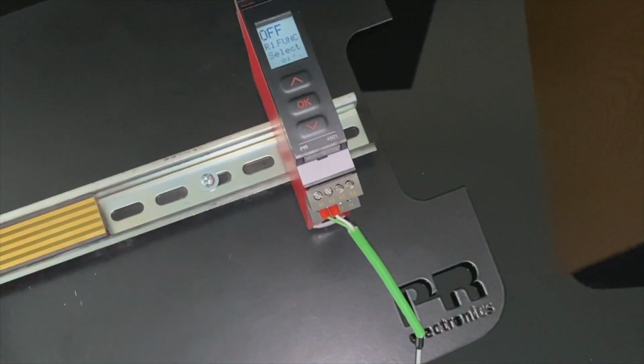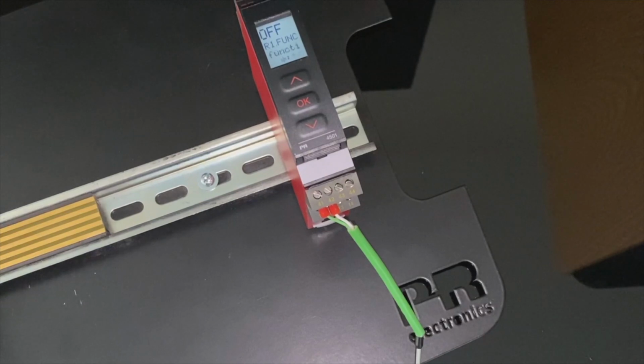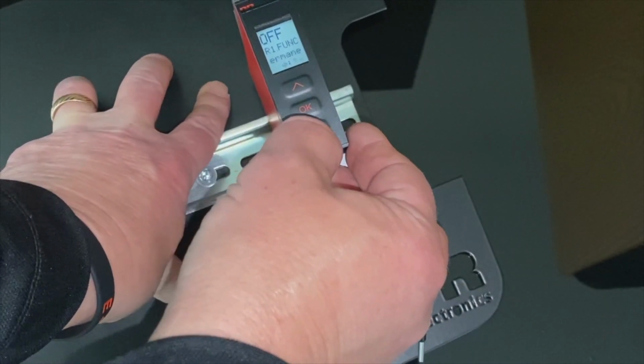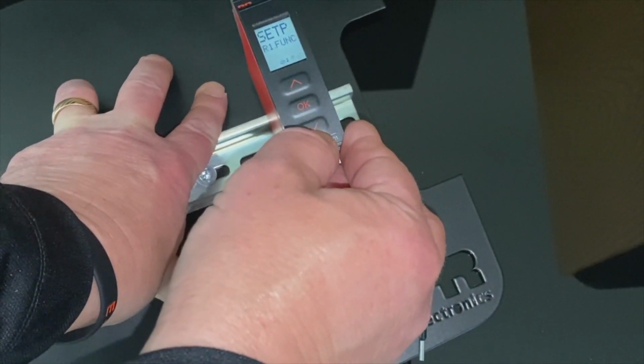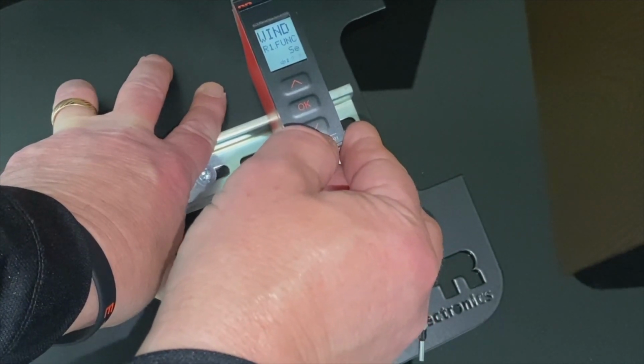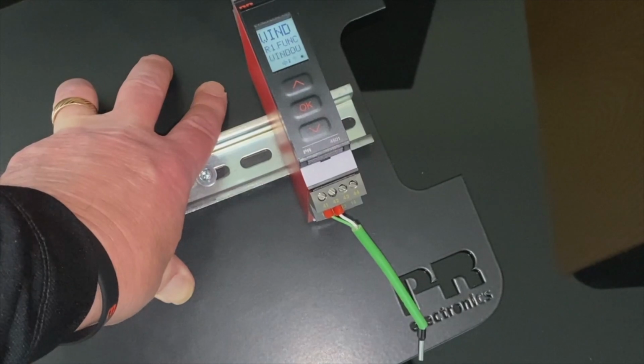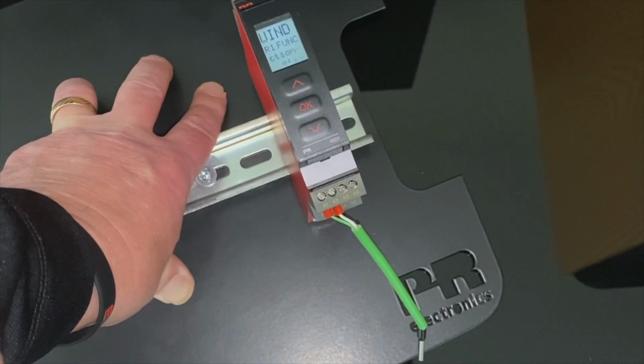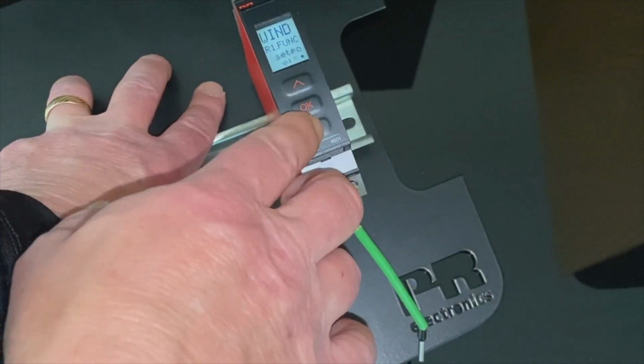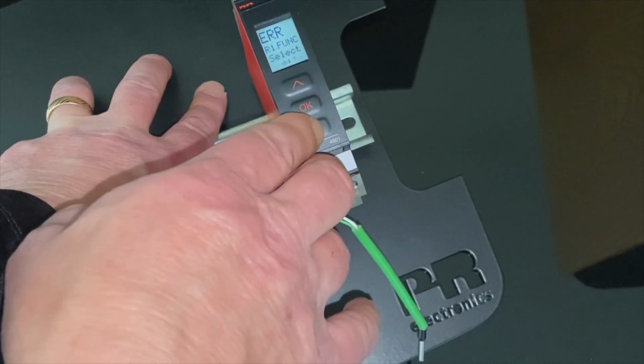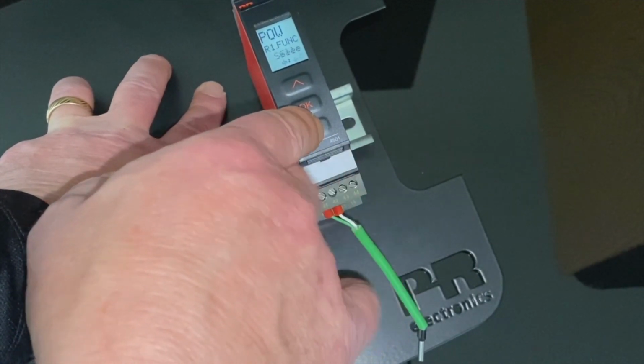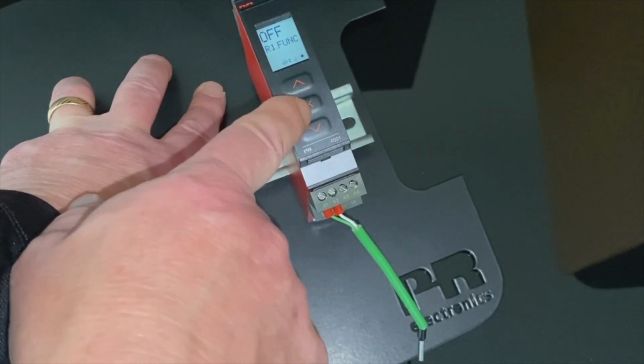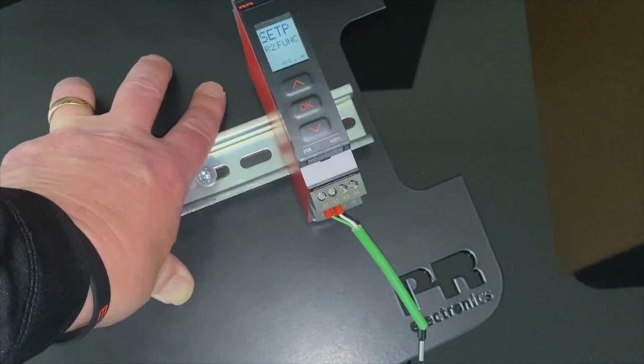Now, we have relays, 2 relays here. The relays each have 5 different functions. Firstly, you can turn the relay off. There is a set point function, a window function, and if you're not familiar with a window function, just picture a window. You've got a frame on either side. You set your area inside that frame, and if the limits or the values exceed either side of that frame, your relay will engage. There's an error function and a power function. So what I generally do with my demo of the relays, I turn relay 1 off, and then I work on relay 2.